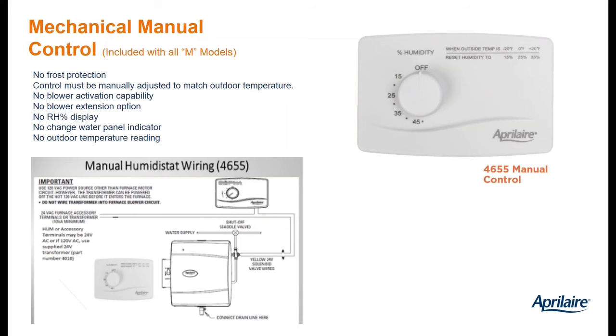So now you're going to have to see what accessory terminals are available in your HVAC system in order to prevent the humidifier from running unless you've got a fan call or a heat call. You're going to have to look and see, do I have EAC terminals, which are typically energized with a blower call? Some manufacturers make those 24 volts, some make them 120. If they're 120, you have to step them down to 24 volts with the included transformer. Or do you have HUM terminals? HUM terminals are typically energized with just a heat call. Are they 24 volts or 120? If they're 120, you've got to step them down with the transformer. So every installation is potentially different.